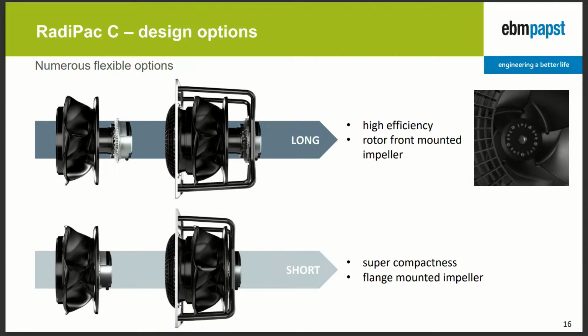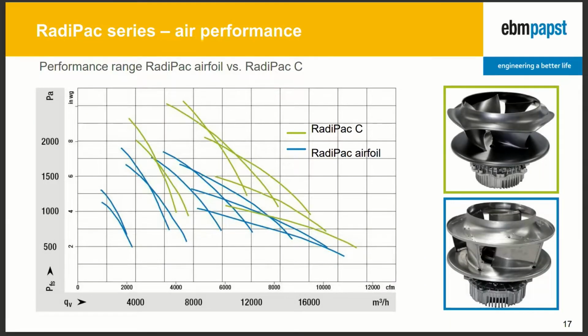Space is limited, but this also costs a certain amount of efficiency. Therefore, we have taken the motor out of the impeller and created a so-called long version, and this one offers the best efficiency because the motor is not disturbing the airflow through the impeller. So comparing this new product with the predecessor, we achieved an improvement in the overall performance.